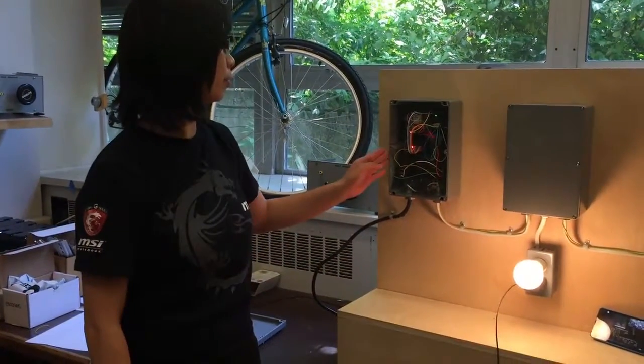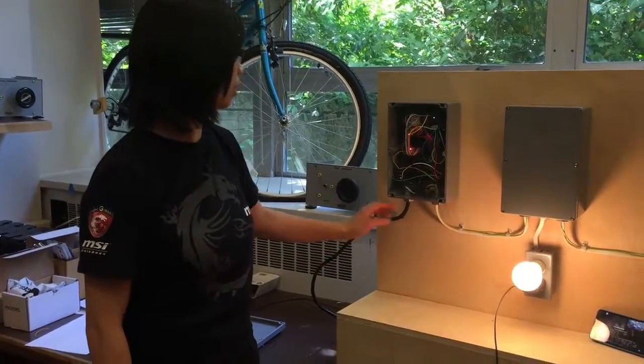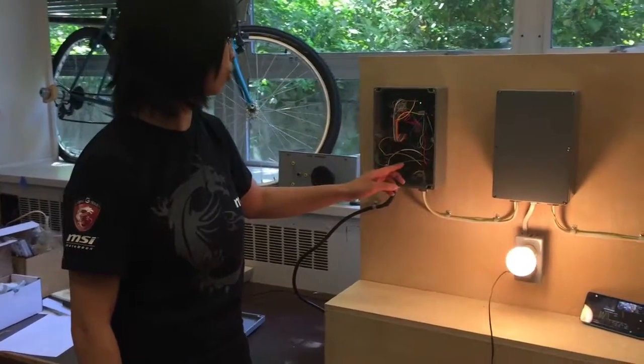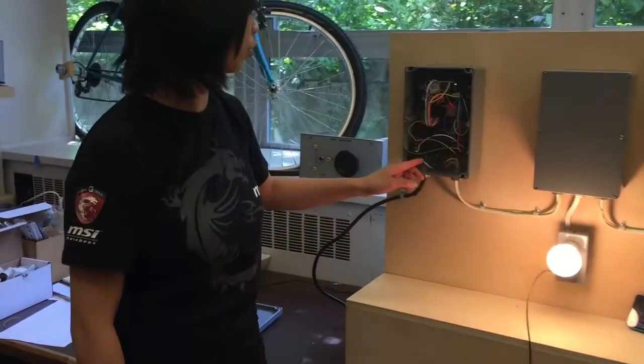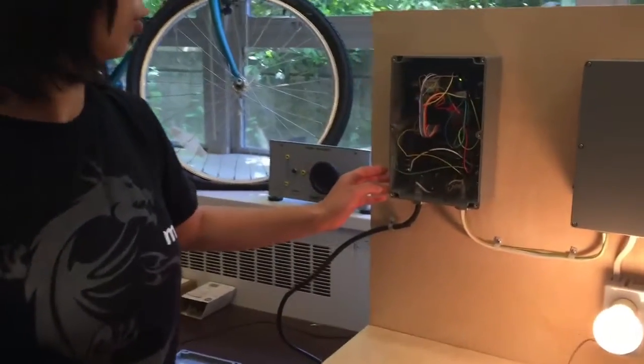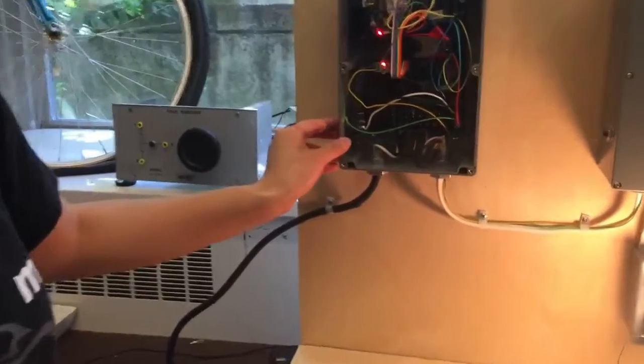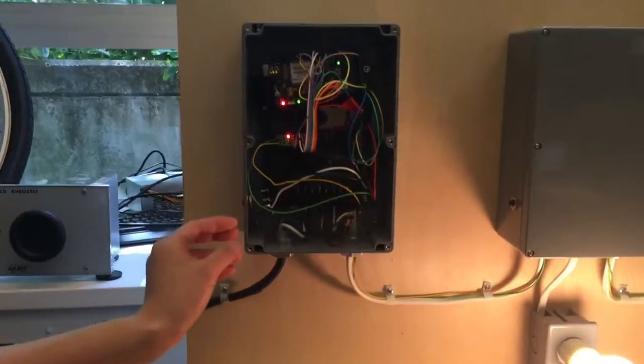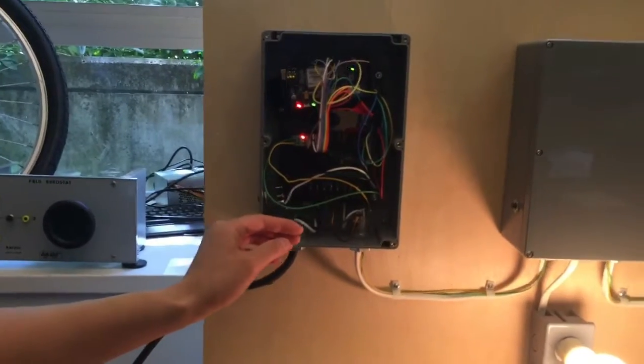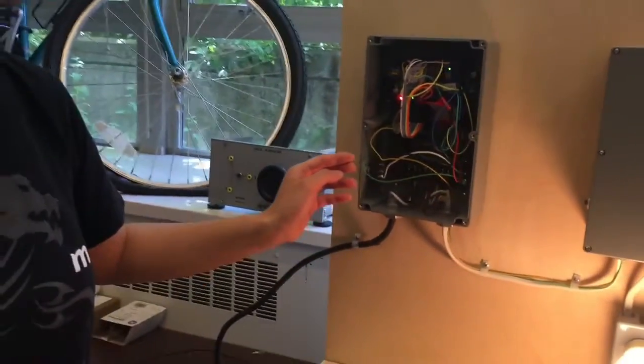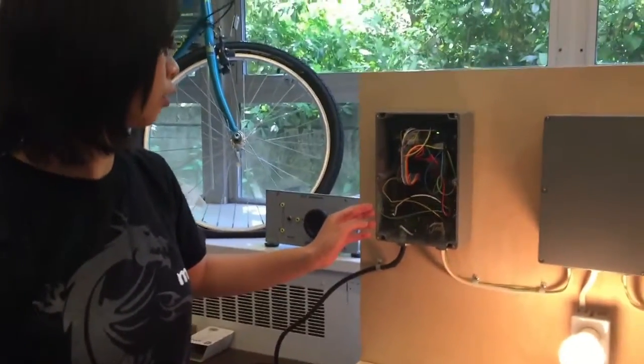In our smart metering system, high voltage comes into this line, going into a terminal block, then through a circuit breaker which catches any faults. We can reset it outside of our enclosure, so we don't have to open it. It also hits the relay, which disconnects and reconnects the load.